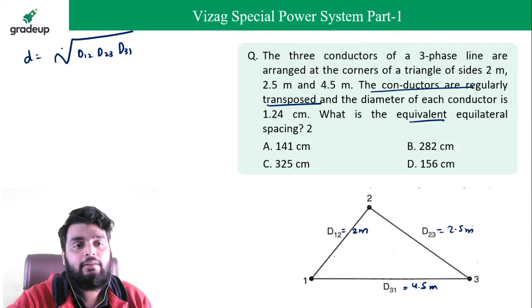Okay, they are asking you for the equivalent equilateral spacing. If I convert this particular triangle into an equilateral triangle, what will be the spacing? That will only come if your line is transposed. If your line is not transposed, then you cannot find the equivalent equilateral spacing. So beta, remember, it will be the geometric mean of these distances D12, D23, D31 raised to power 1/3.